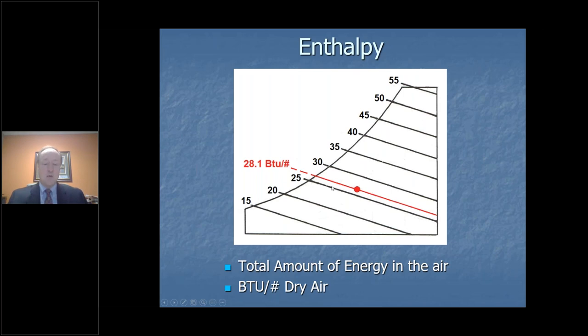These lines on the psychrometric chart overlap the wet bulb temperature lines, but they are not parallel throughout the whole chart. So you need to be careful when you're following the enthalpy line. But that's the amount of energy. As you add moisture, let's say you started here at 75 degrees with no moisture, you'll see you're at about 17 BTUs per pound. But as you add moisture, then you are also adding BTUs. So when we look at this BTU number, that's total BTUs derived from the sensible load or the heat gain, as well as the moisture load or the latent gain.